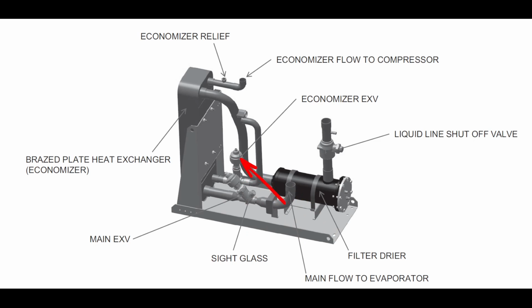This was an economizer valve, and this is used in a few different types of systems. Not necessarily the braze plate style, but using the EEVs for just various control. This used to be a TXV on older systems, and this has been upgraded to an EEV style. But just to give you a picture of how they're implemented: our liquid line is coming in through here. We see our filter dryer going through our economizer, and then we're passing through. But you can see the body. We have a sight glass here. This body also has a sight glass over on the side. And then we have our motor assembly and our head assembly threaded onto that valve body.